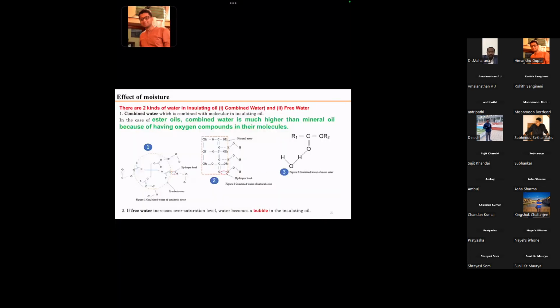For the effect of moisture, we found there are two kinds: combined water and free water linked with the oil molecules. If you talk about monoesters and natural ester, forgetting synthetic ester for now, the combined water which is combined with the molecule in ester oil is much higher than in mineral oil, because of having oxygen compounds in their molecules. Mineral oil does not have the capacity to carry high moisture or water content, but FR3 or ester oil has the capacity to tolerate or include much higher moisture compared to mineral oil.